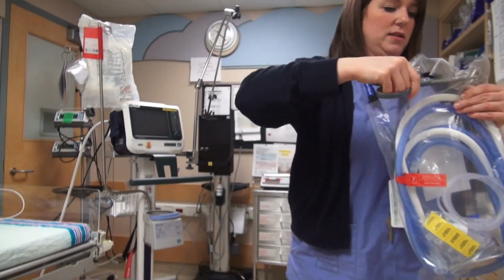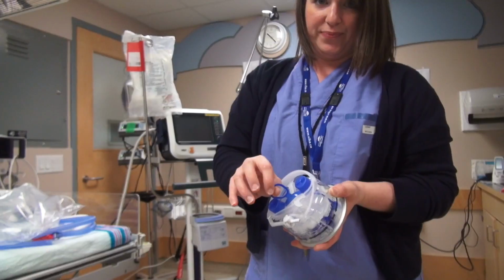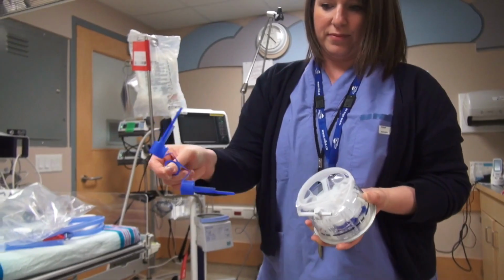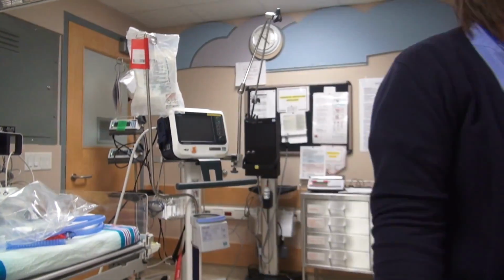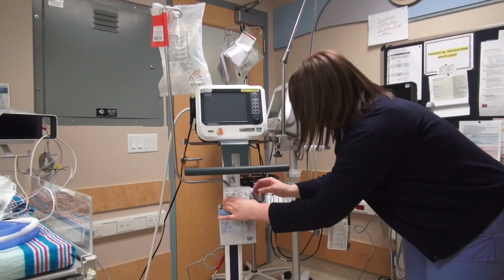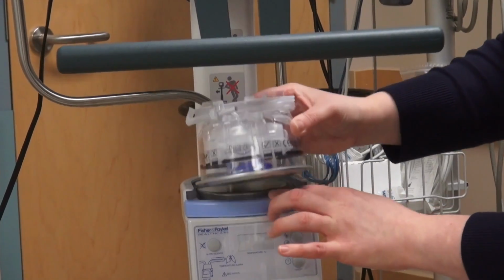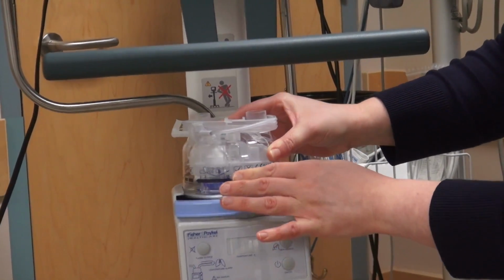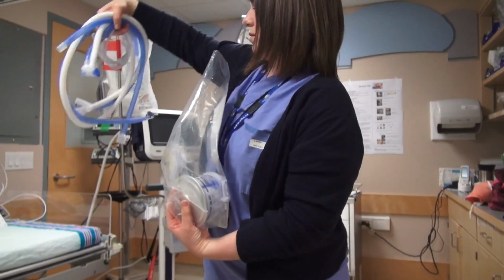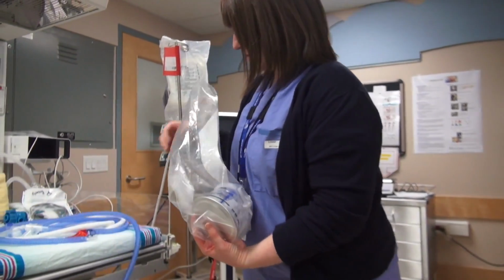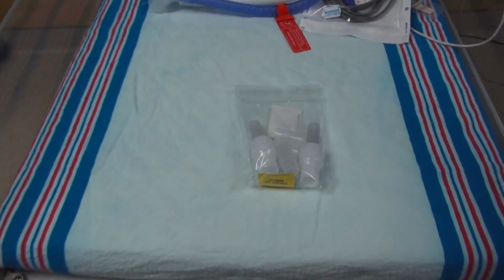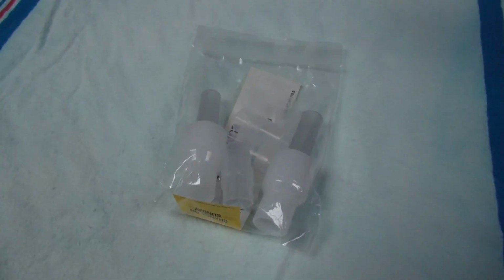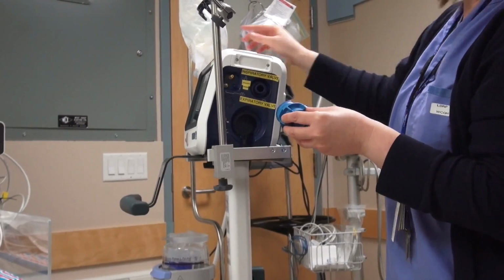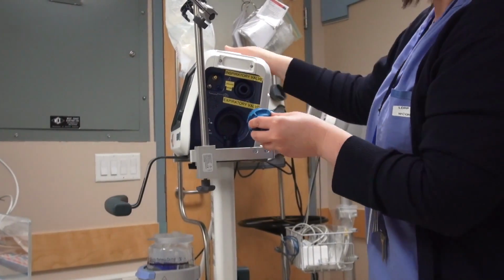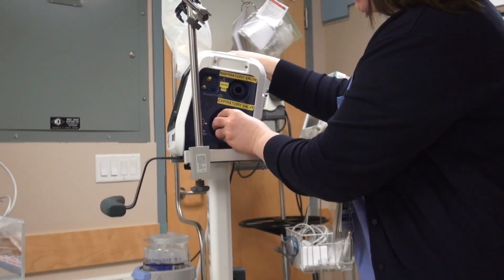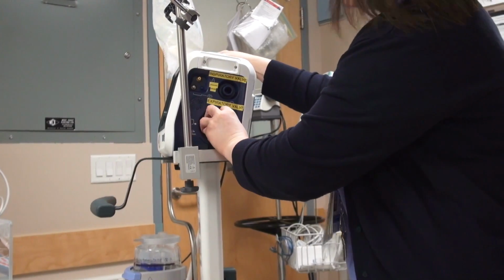Step 1. Open the neonatal circuit bag. Remove the blue plug on the top of the humidifier chamber and discard it. Slide humidifier chamber into the humidifier. Reminder to keep all of the other parts in the bag. If babe deteriorates and needs to be intubated, you will need the additional pieces. Insert expiratory valve into the side of the Hamilton ventilator. Once you put it in, you move to your right and you'll feel a click.